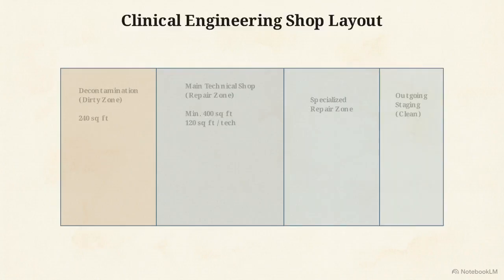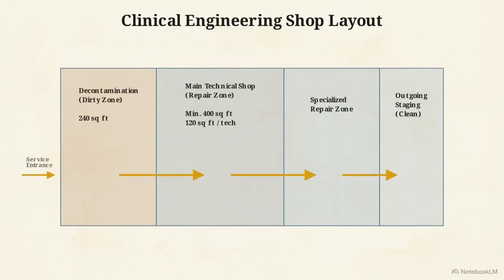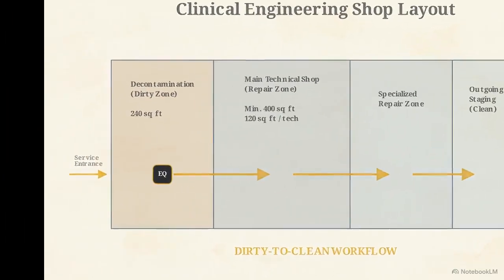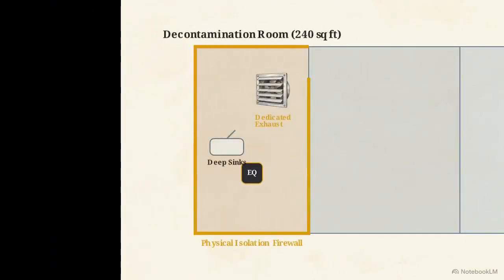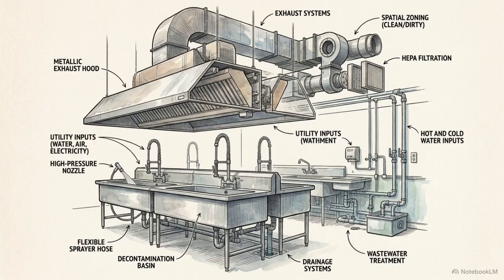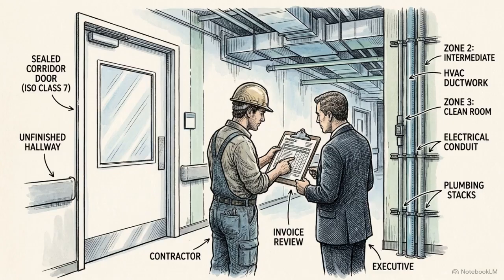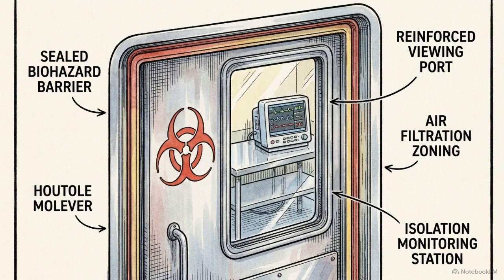This floor plan outlines the mandatory physical layout of a clinical engineering shop. The non-negotiable foundation of this space is a strict dirty-to-clean workflow. Equipment coming off the floor goes straight into a dedicated decontamination room. This requires ground floor plumbing for deep sinks, spray nozzles, and a completely separate exhaust ventilation system. That infrastructure carries a significant cost, but it serves a critical function, stopping healthcare-associated infections right at the door before they can contaminate clean equipment.